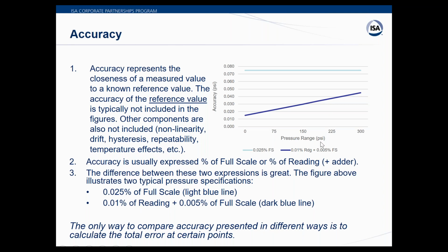But notice on the graph that I'm putting things in PSI. When you're doing this type of analysis, I just want to make the point that you really need to get out your calculator and take these kind of crazy numbers and turn them into engineering units that apply to your process or your instrument and the way it's ranged. But you can see in this case, this is quite a bit more accurate, by more than double, than what this line represents. So this is a good statement, but this is really good. Okay.